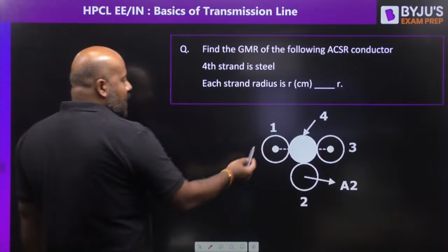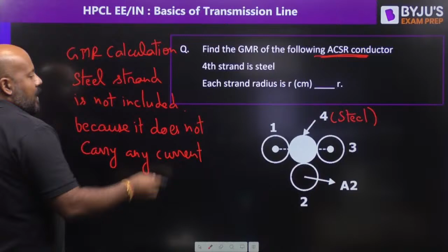How are you going to solve it? This is strand number 1, 2, 3 and 4. Because it is an ACSR conductor, this fourth strand is going to be made of steel. Please remember this concept: in the GMR calculation, the steel wire or steel strand is not included. Why is it not included? Because it does not carry any current. So if I have to write the GMR for this construction, it is going to be the GMR for the first strand multiplied by the GMR for the second strand and the GMR for the third strand.